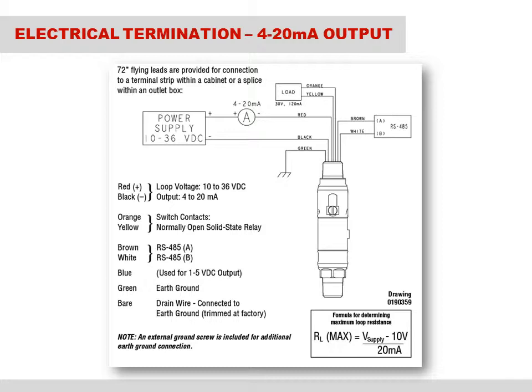One of the most important wires is the green insulated conductor. It is connected to earth ground. A very good earth ground is a solid copper rod driven 3 or more feet into the soil, into the ground. Note that the blue insulated conductor is not shown on this slide. That is because the blue wire is not needed for a 4 to 20 milliamp output. So onward we go to the next slide to see how the blue wire is used.